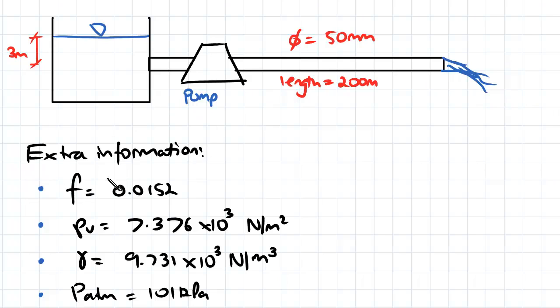In terms of extra information we have, we've got a friction factor of 0.0152. At 40 degrees, our vapor pressure is 7.376 times 10 cubed newtons per meter squared. Our unit weight is 9.731 times 10 cubed newtons per meter cubed. And the atmospheric pressure is 101 kPa.